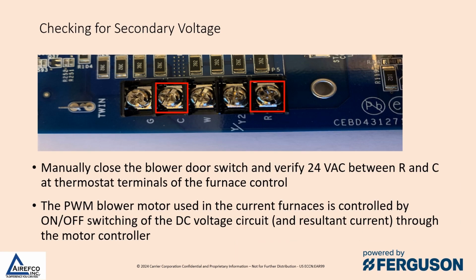You want to check for secondary voltage on the control board, and you want to manually close the blower door switch and verify that you have 24 volts AC between R and C at the thermostat terminals of the furnace control. The pulse width modulating blower motor used in the current furnaces is controlled by the on-off switching of the DC voltage circuit and resultant current through the motor controller. All of the tests that we're going to talk about in the next few slides will be between the brown, yellow, and orange wire and the common terminal on this thermostat strip.